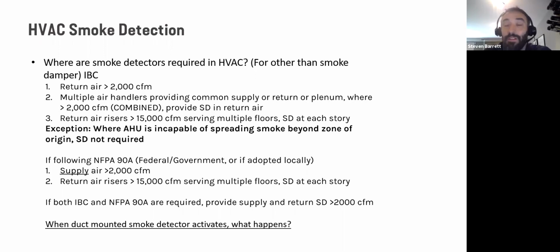One classic example of that might be a gymnasium with a big rooftop unit and a big wide open gym. So let's say a fire starts in the gym and smoke starts spreading. The air handler is going to continue to provide supply air and return air, but it's not spreading smoke throughout the building. The smoke's already there. It's already in the room, and you're not spreading it anywhere else. So that's the reason why the code allows you to omit the smoke detector in that system. You could, of course, provide it, but it's not required. And there may be other cases too that are maybe not quite as straightforward as a big gymnasium. But if you do meet that section of the air handler being incapable of spreading smoke beyond the zone of origin, you can omit the smoke detector in the return air.